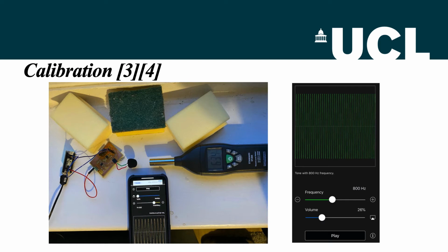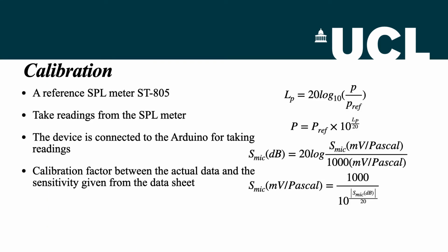We used an app on a mobile phone that is able to play tones at different frequencies and different amplitudes. The microphone was connected to an Arduino for taking voltage readings for a certain level of sound, then the reading from the SPL meter in dBA is called the sound pressure level or the acoustic pressure level. This is defined as the pressure difference caused by the vibration of a sound wave passing through the medium. Then we convert the reading into pressure and combine it with the reading from the Arduino, and we get a value in millivolt per Pascal. The datasheet of the microphone provides a sensitivity in decibels or millivolt per Pascal, and as a result, the calibration factor can be calculated at each frequency value.